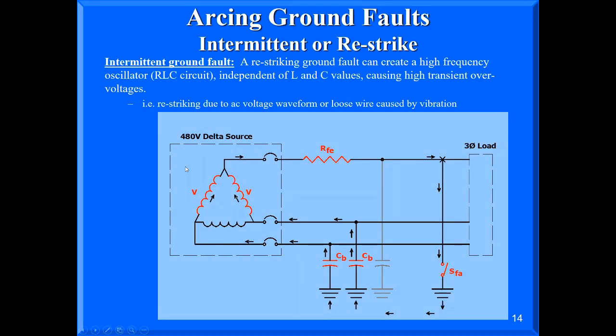The reason is, you have an ungrounded system, for example, where I've got capacitance because I've got cables next to each other, but I don't have anything else. And it's literally like me turning a switch on and off right here. And what happens is, I could literally be charging these capacitors. On an ungrounded system, you could see 6 to 8 times over voltages. I've got a customer here in Atlanta, a 600 volt ungrounded paper mill, and we've measured over 2,800 volts on that 600 volt system. Needless to say, the equipment's not designed for that.